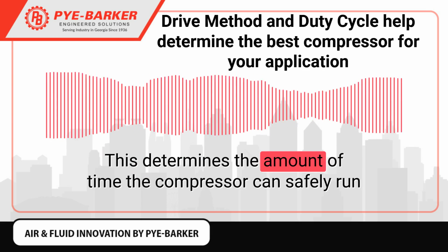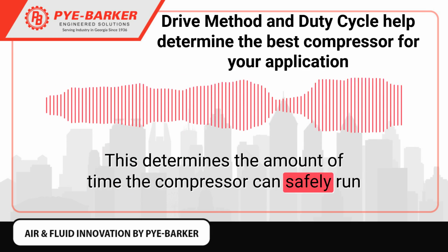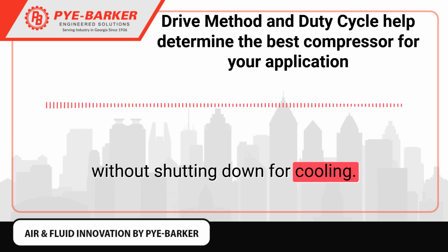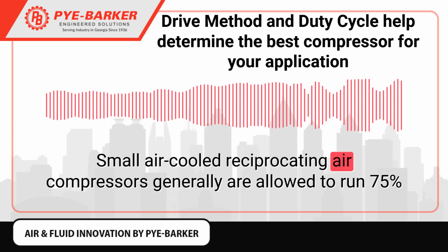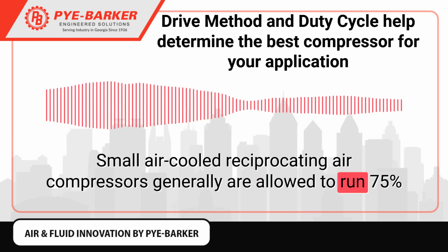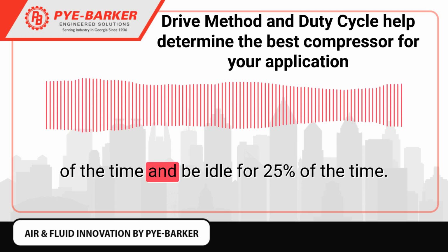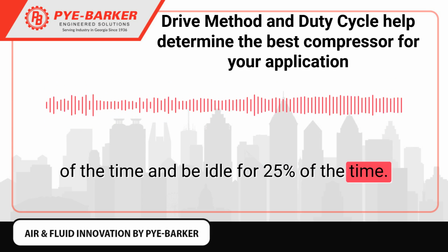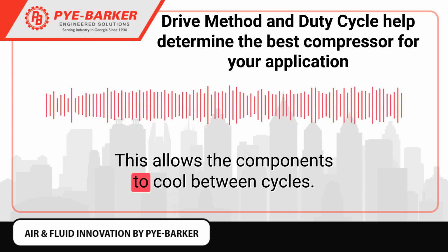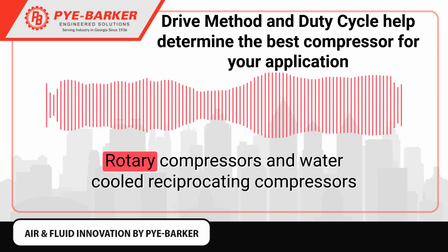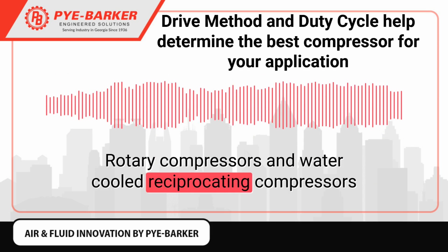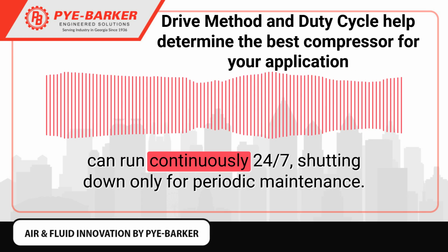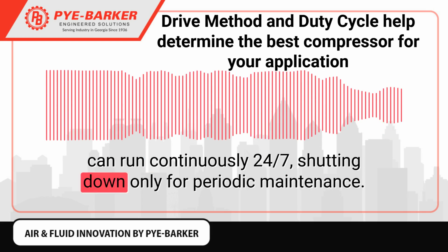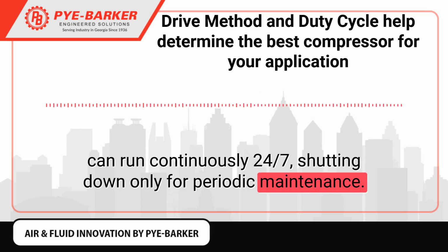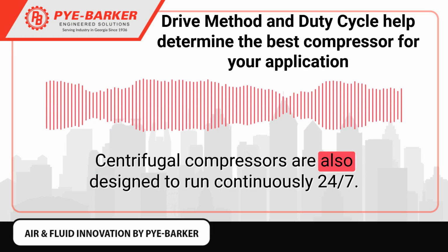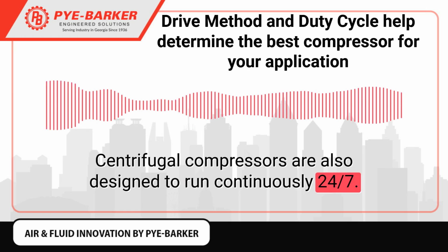This determines the amount of time the compressor can safely run without shutting down for cooling. Small air-cooled reciprocating air compressors generally are allowed to run 75% of the time and be idle for 25% of the time. This allows the components to cool between cycles. Rotary compressors and water-cooled reciprocating compressors can run continuously 24/7, shutting down only for periodic maintenance. Centrifugal compressors are also designed to run continuously 24/7.